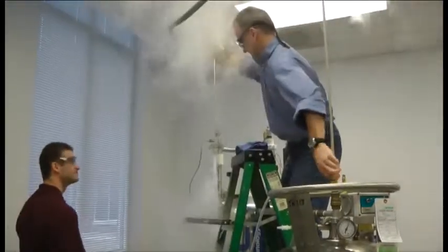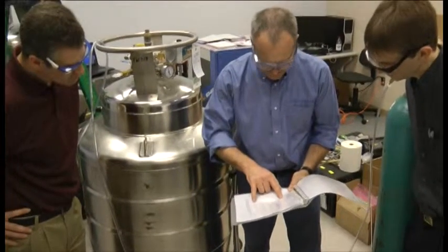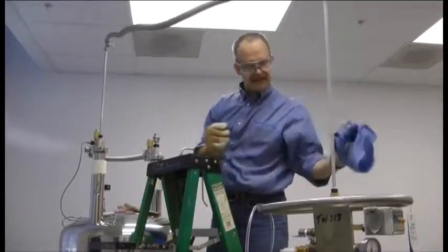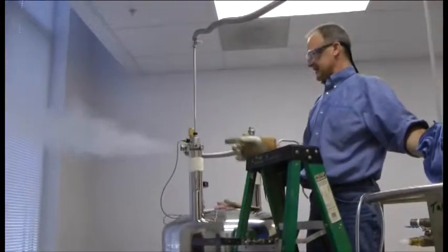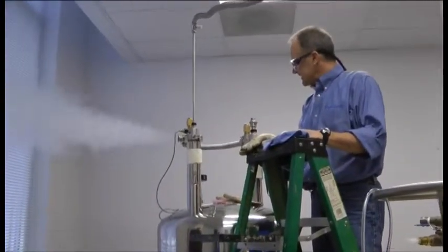It's pretty typical for these instruments to go at least around 10 or 15 years without an issue, and then after that, maybe you have to re-engineer the current a little bit or do whatever to get things going again. But you can probably get 20, 25 years on an instrument like this without any kind of major problem.